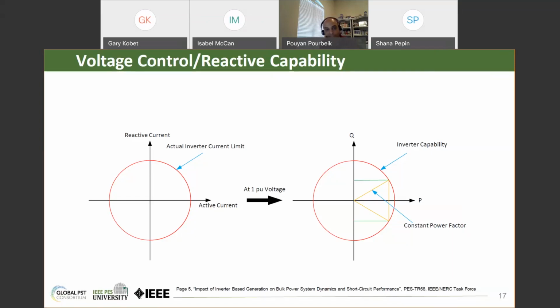And again, I put Q and P there. These are really currents, so the actual Q will also vary as a function of the grid voltage. But still, the concept is, if not properly defined, you may end up limiting the device beyond what you really want to, if that makes sense. So the gap right here really was having a well-defined expectation in terms of reactive support.